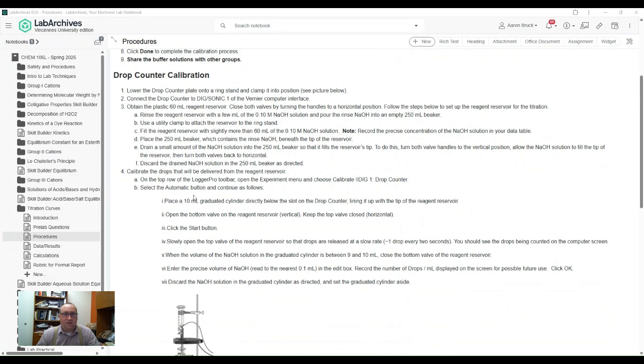I'm just going to move myself over here so that you can see. For the drop counter itself, we need to make sure that it's set up properly, that the drop counter is positioned so that the drops falling out of the reservoir actually break the beam of light and record accordingly. We also need to figure out the value of the drop. We need to correlate a volume in milliliters to a single drop. That's really what this particular calibration is for.